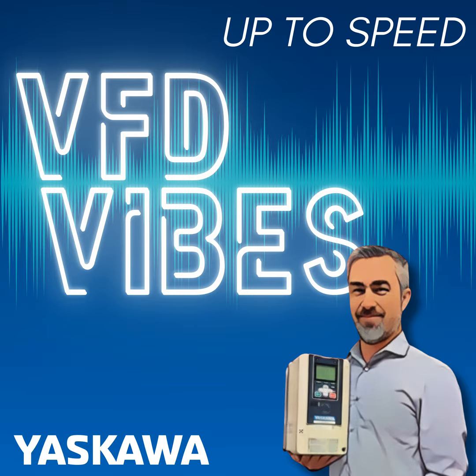Nobody wants to be the butt of jokes for the rest of their career. That's right. So always verify that the power is correct. And how can you do that? Well, the drive has a nameplate on it. It's clearly indicated what you have coming in. Measure the input voltage before you turn on that switch, and then also verify that the wires are landed properly.